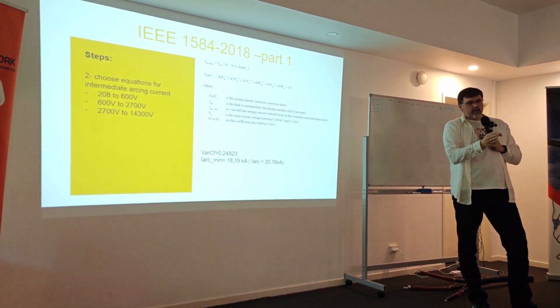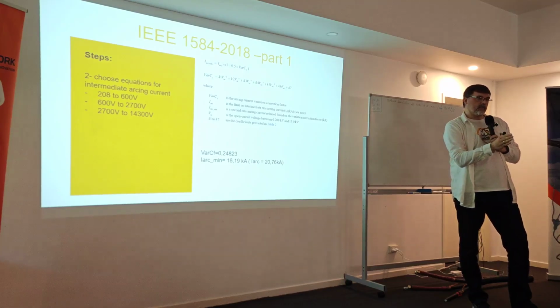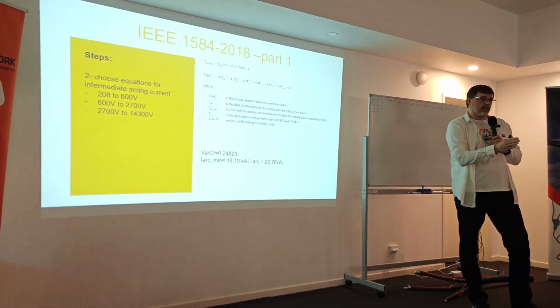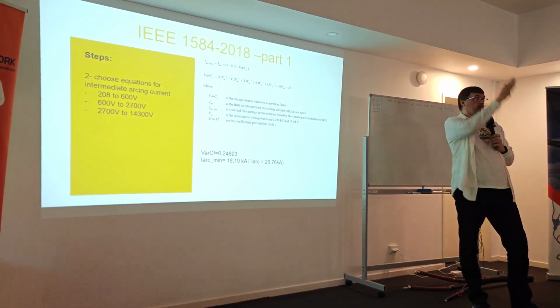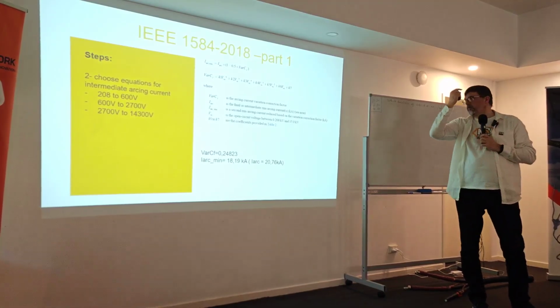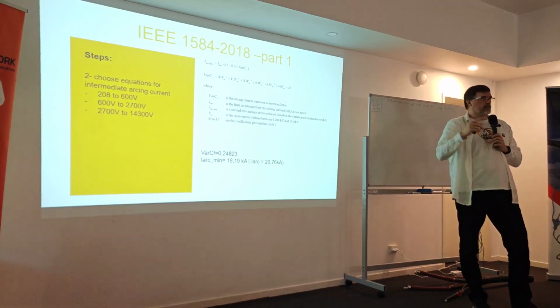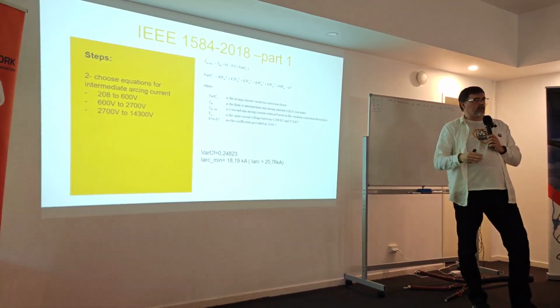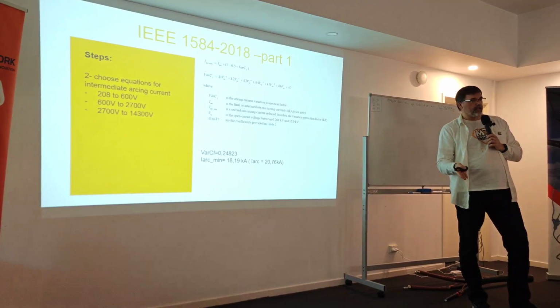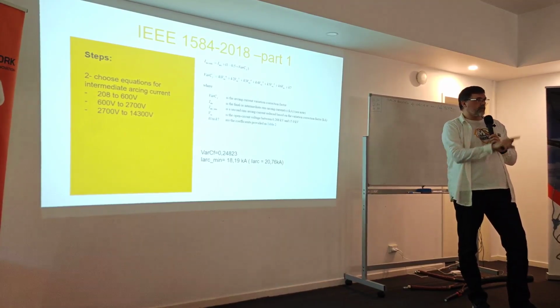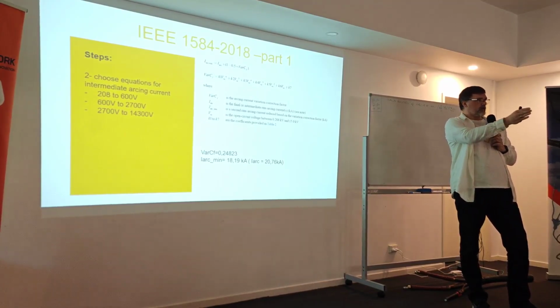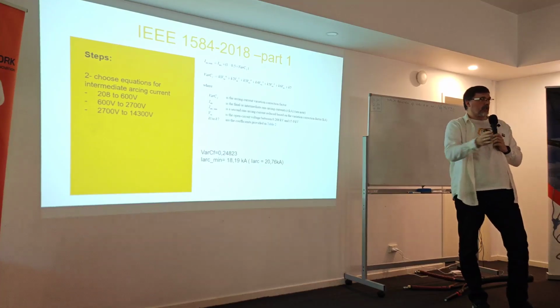So we are somewhere plus minus, and it's very likely that you are a bit positive on the current, and if you reduce it a bit, you might find out that your tripping times are much higher, which I will try to show you an example later if I can show it. So it's more about the protection. We just try to find out the lower current and then see if this lower current is not a problem for the protection, because you might be on the edge of the settings. So this is like a double check.